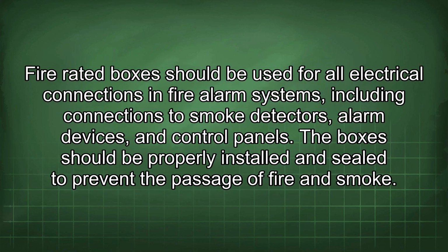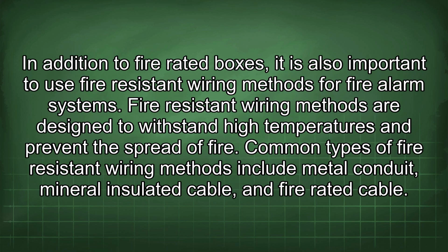Fire-rated boxes should be used for all electrical connections in fire alarm systems, including connections to smoke detectors, alarm devices, and control panels. The boxes should be properly installed and sealed to prevent the passage of fire and smoke. In addition to fire-rated boxes, it is also important to use fire-resistant wiring methods for fire alarm systems. Fire-resistant wiring methods are designed to withstand high temperatures and prevent the spread of fire. Common types of fire-resistant wiring methods include metal conduit, mineral insulated cable, and fire-rated cable.